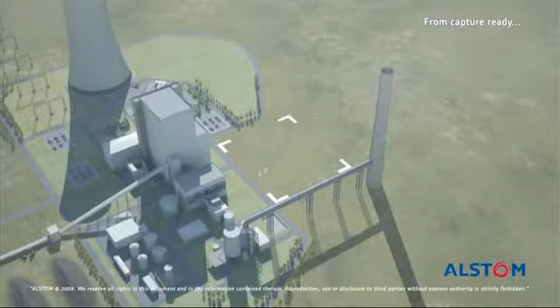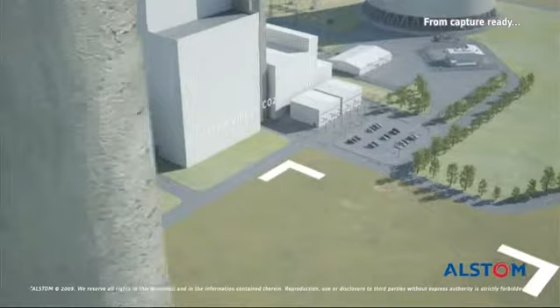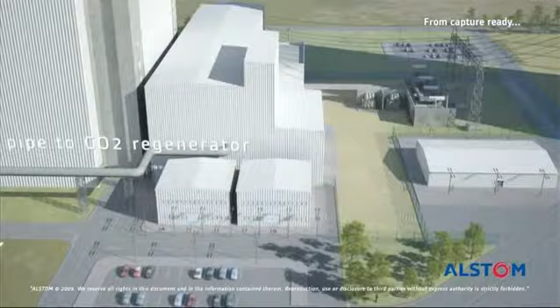That's the space we have reserved to capture the CO2. You also study the storage option, which needs to be validated before you can kickstart your capture operation. You do some preparations on your turbine hall, with tie-ins to prepare and maybe adapt the turbine so it can take steam for the capture unit. You also reserve space in your switch yard to install new transformers, since you'll need power for compressing the CO2, for instance. Once you decide to go for capture, you can install those new transformers.